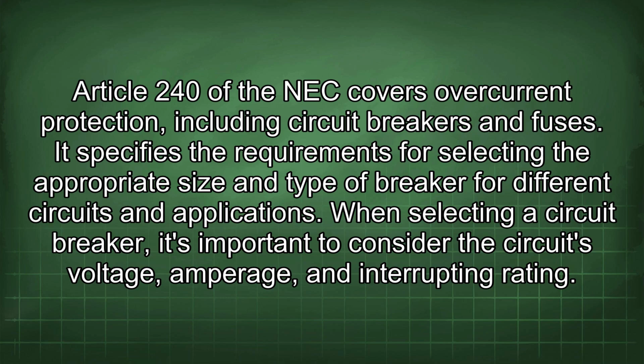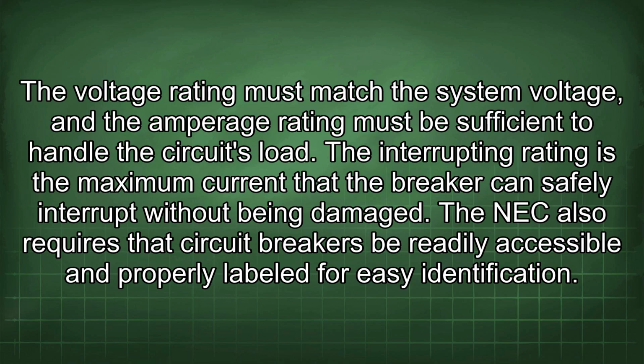It specifies the requirements for selecting the appropriate size and type of breaker for different circuits and applications. When selecting a circuit breaker, it's important to consider the circuit's voltage, amperage, and interrupting rating. The voltage rating must match the system voltage, and the amperage rating must be sufficient to handle the circuit's load. The interrupting rating is the maximum current that the breaker can safely interrupt without being damaged.